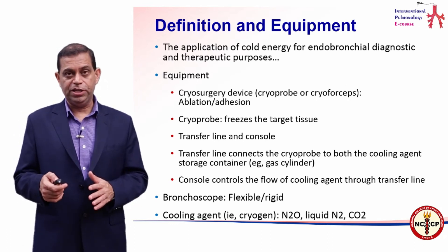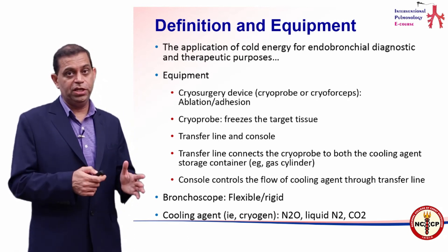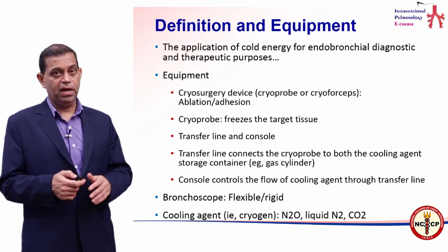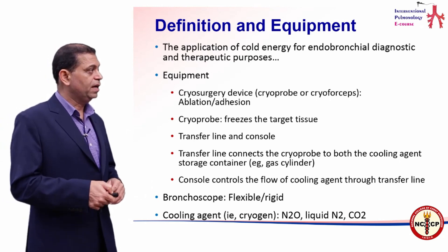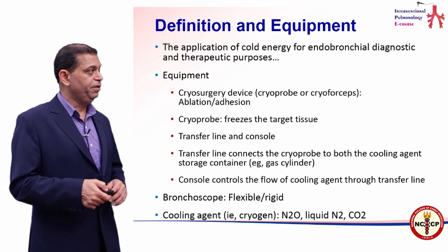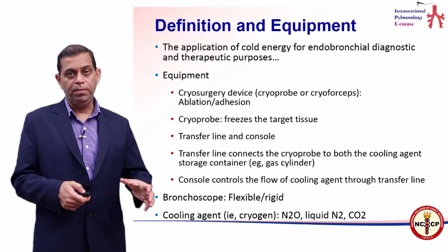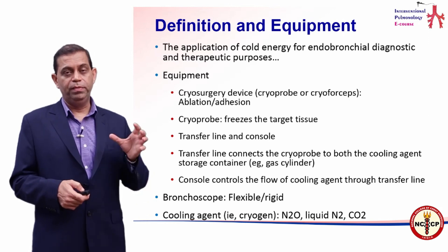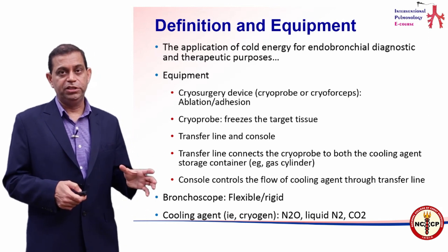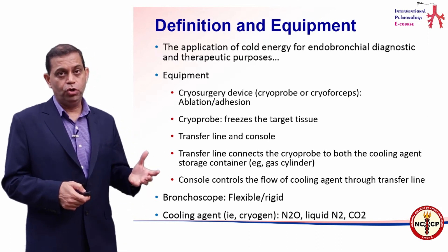We have the cryosurgery device, which is the cryoprobe. It is used for various applications such as ablation for therapeutic aspects, and adhesion which can be therapeutic or diagnostic. The cryoprobe basically freezes the target tissue and does its job by making it cold-destroyed or cold-attached, and that leads to the therapeutic component.